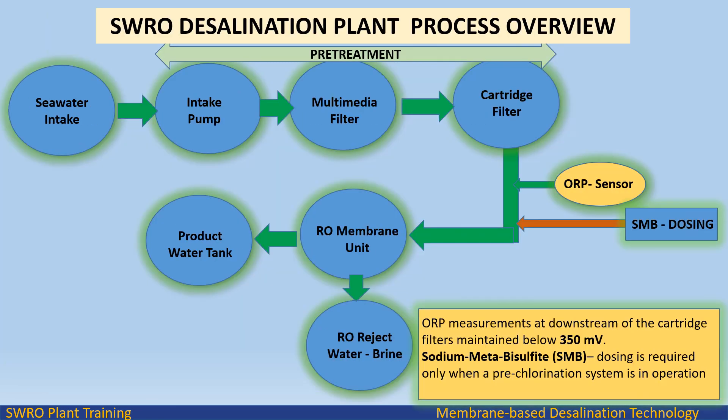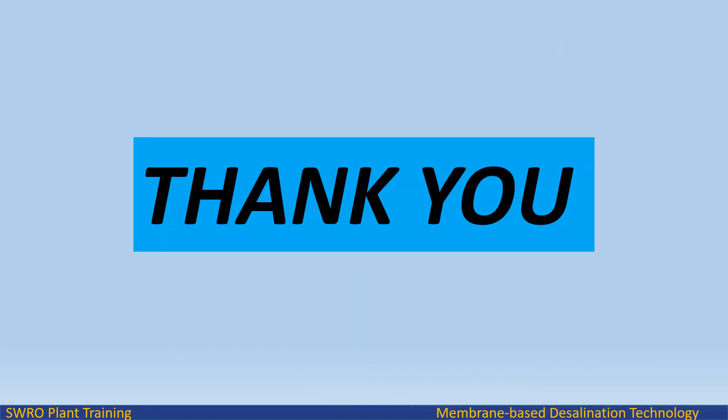Sample point location for ORP sensor and SMB dosing in RO plant: ORP measurements at downstream of the cartridge filters should be maintained below 350 mV. Sodium metabisulfite (SMB) dosing is required only when a pre-chlorination system is in operation.